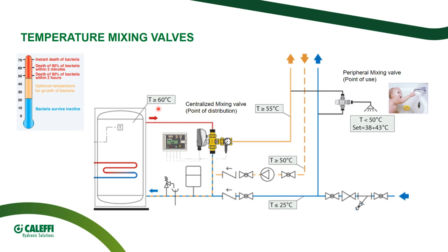At some certain temperatures that we can identify below 20-25 degrees, Legionella is there, but is not active, so it's not dangerous for the human being. Above some certain temperature that we can identify as 48-50 degrees, Legionella starts having issues and dying. So the higher is the temperature, the quicker is the death of this bacteria. So just to give you an example, at 70 Celsius degrees, the death of the bacteria is almost instantaneous.